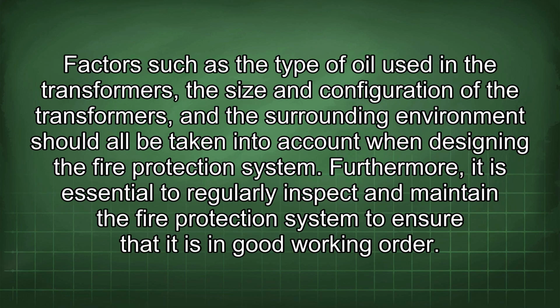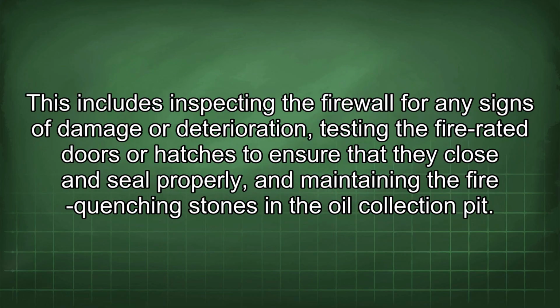Factors such as the type of oil used in the transformers, the size and configuration of the transformers, and the surrounding environment should all be taken into account when designing the fire protection system. Furthermore, it is essential to regularly inspect and maintain the fire protection system to ensure that it is in good working order. This includes inspecting the firewall for any signs of damage or deterioration, testing the fire-rated doors or hatches to ensure that they close and seal properly, and maintaining the fire-quenching stones in the oil collection pit.